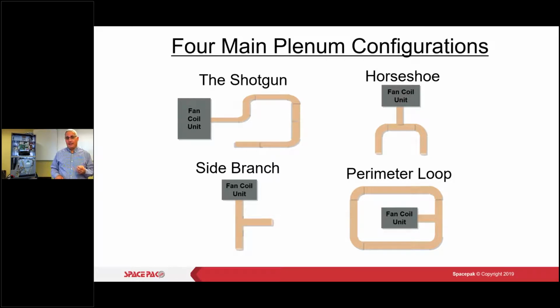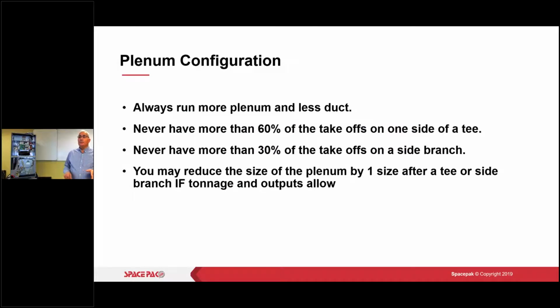I can't stress that enough. If everything's always down in the center, then my 2-inch drops get longer. And now there's the chance I may have to add more drops because of the length of run to those rooms. Okay. So always run more plenum. So you can never have 60% takeoffs on one side of the T, and you never have more than 30% takeoffs on a side branch. Right? We can reduce the size of the plenum, as it says right there, by one size after a T or a side branch if tonnage and outputs allow. So if the majority of my output is on one side and I have a T, then I can reduce after that.